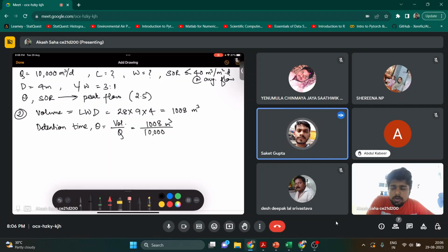Yes, tell me. What we conclude: the required area is less and the actual area is more. Yes, see, the actual area should be equal to or a little more than the required area. So if my required area is 10, I can provide 15 also. That is not a problem. But it should not be too high. So instead of 250, we are providing 252. That is okay. That is not a problem.